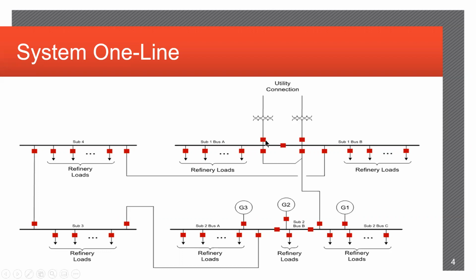So there are obviously other circuit breakers in the system, but there's only the circuit breakers that are part of the path from any one generator to the utility. There were probably hundreds of circuit breakers in the actual system itself, but we were only monitoring 17 individual breakers that made up the path, or a potential path, from any one generator, either connected to another generator or out to the utility. I hope I answered the question. If not, please let me know.